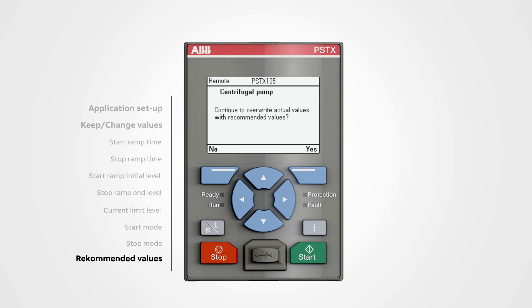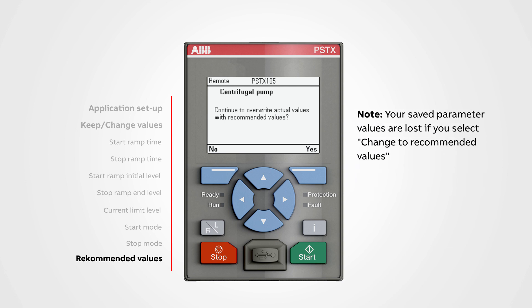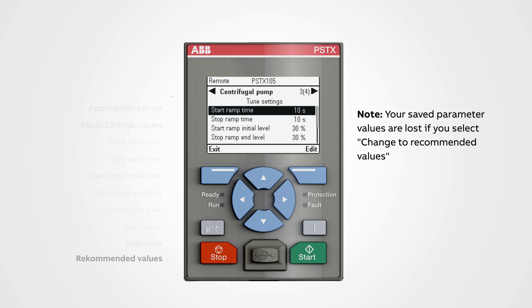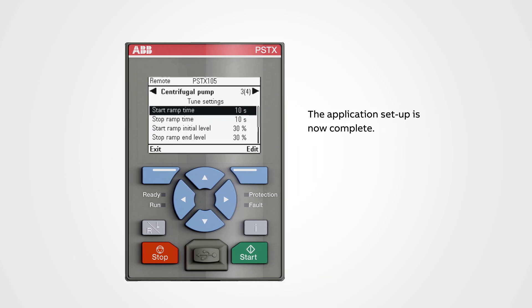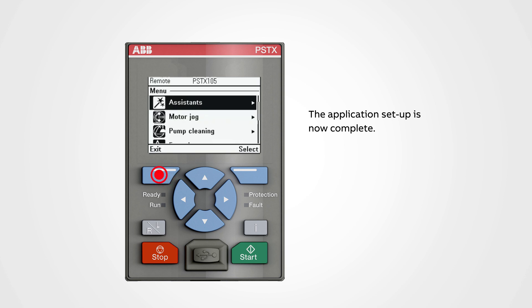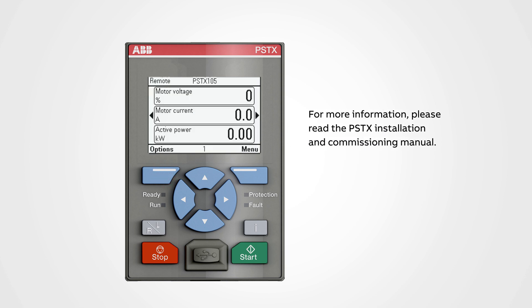Change to recommended values replaces all settings with recommended settings for the centrifugal pump. Push yes to save the recommended settings. Note that your saved parameter values are lost if you select change to recommended values. The application setup is now complete. Return to the home screen with the top left button. For more information, please read the PSTX installation and commissioning manual.